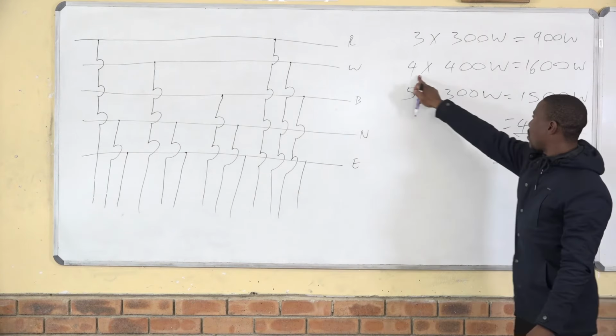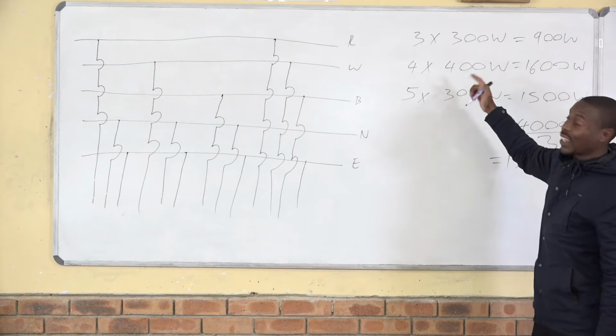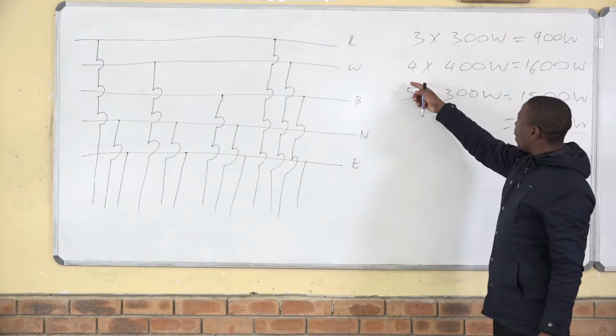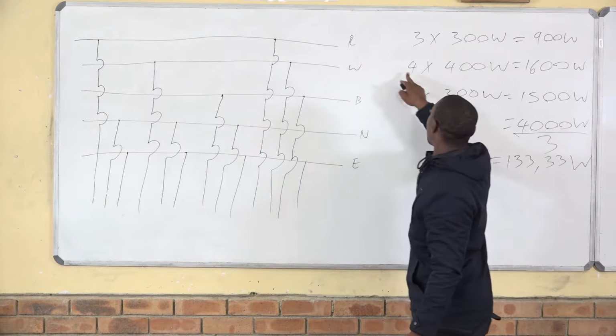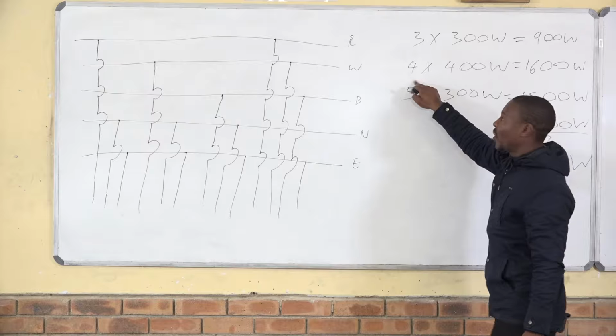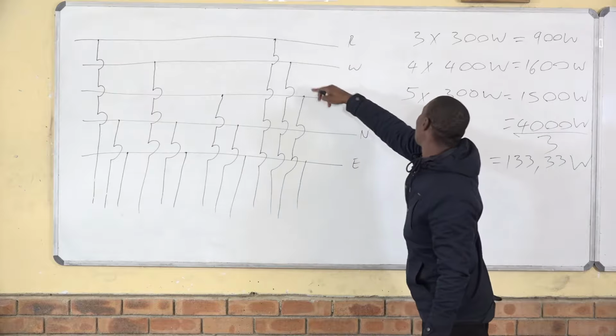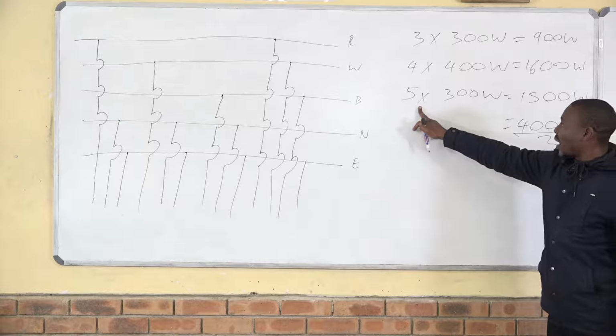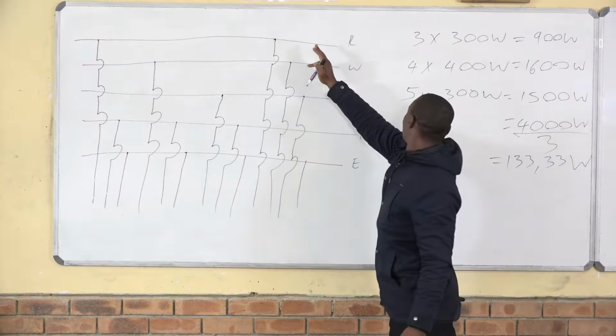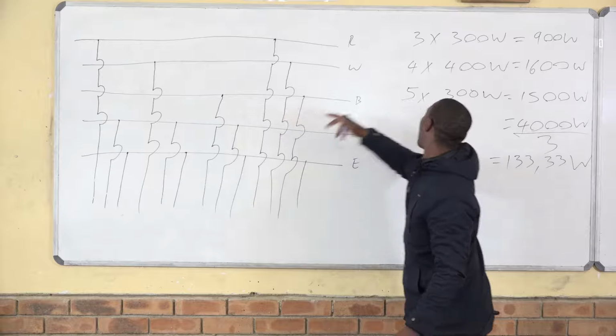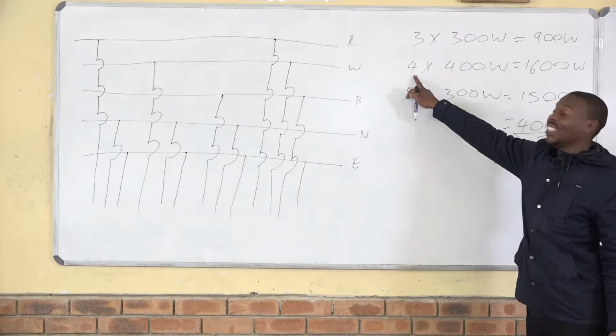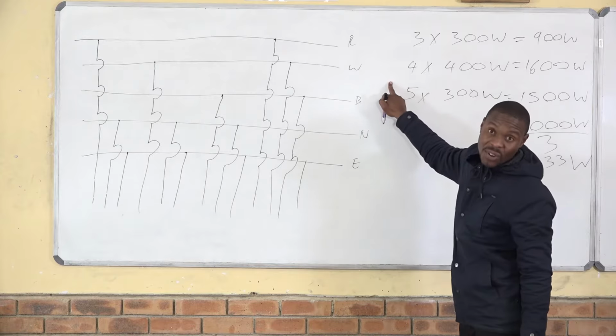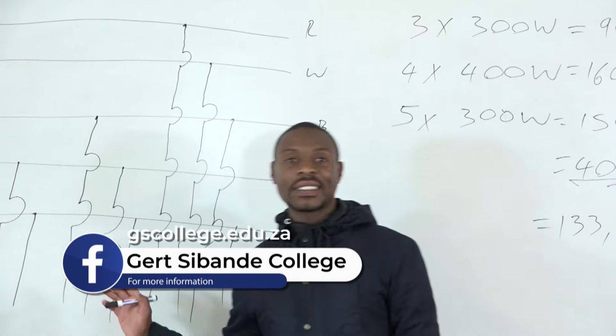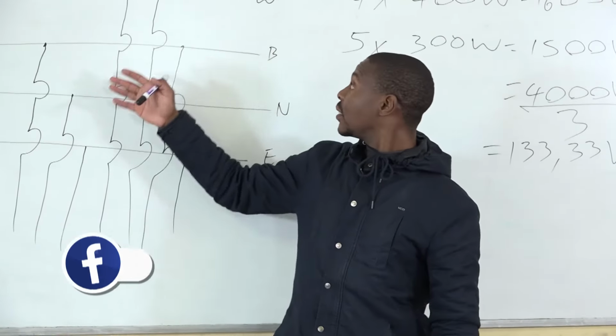Again, you do it. Now remember, now you are having 4 of this other type of load. Then you say 1 for each phase, or you can put 2 for each phase, since here they are saying 4. You can put 2 on each phase and 2 on the other one. Then you come again on this one. Since there are 5, you can put 1, 1, 1, and then you put 2 on the other one where you didn't put 2, since on the first one you put 2, 2. Okay, this is all about load balancing. You are just requested to balance your load through a three-phase 4-wire system. From there you are done.